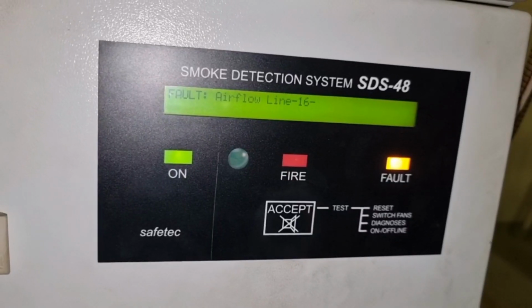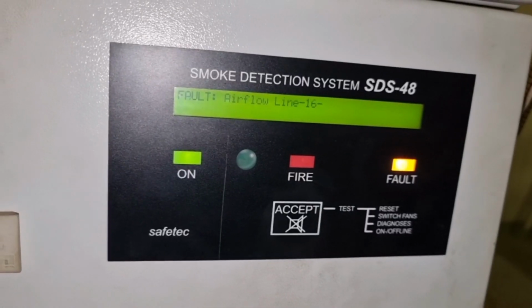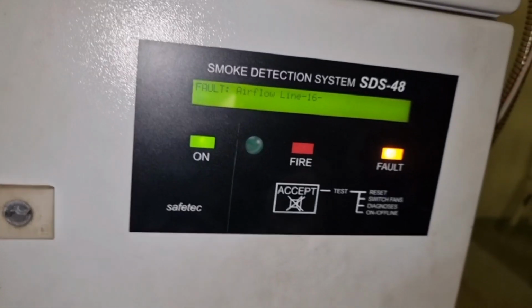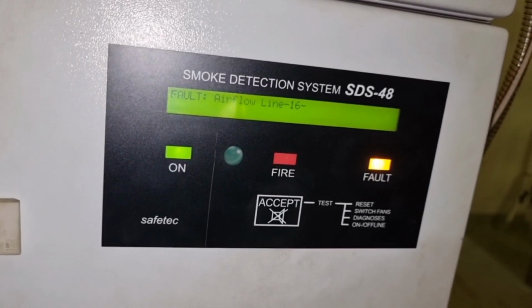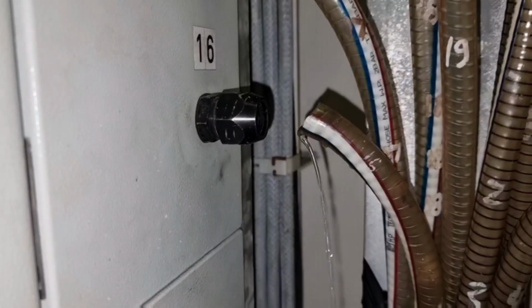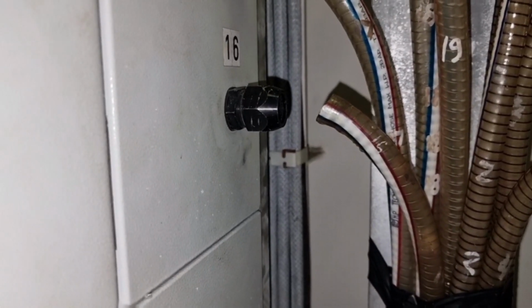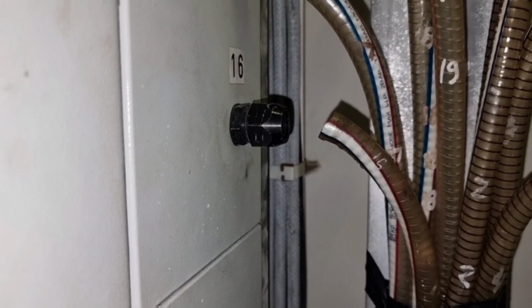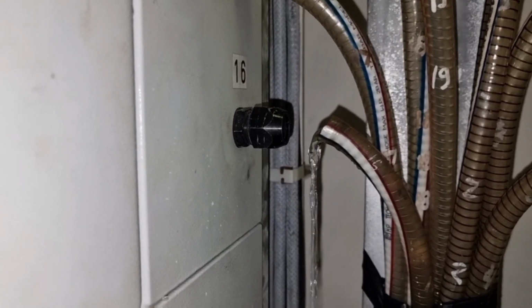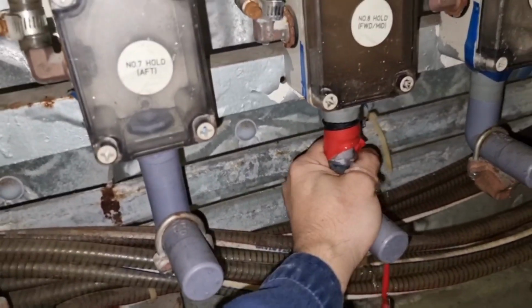Today's troubleshooting is all about our smoke detection system. I was called by the duty officer and he told me that he's having the airflow alarm on line 16. And when I get to the CO2 room, this is what I have found out. The water went inside the panel and flooded the system. So come and join me in fixing this kind of trouble.